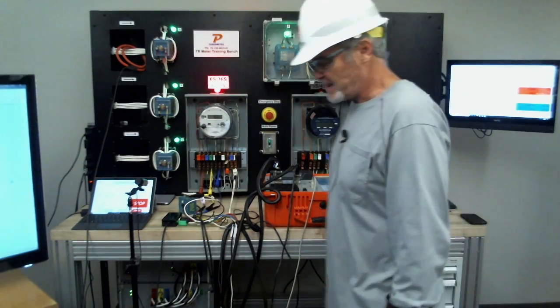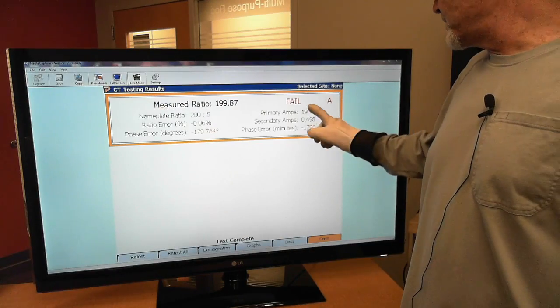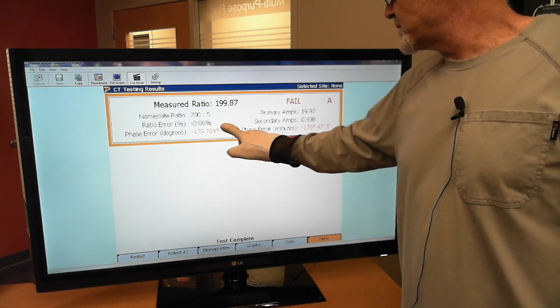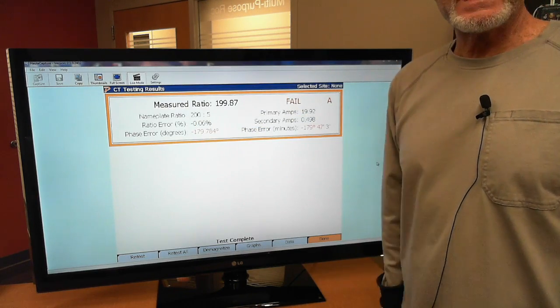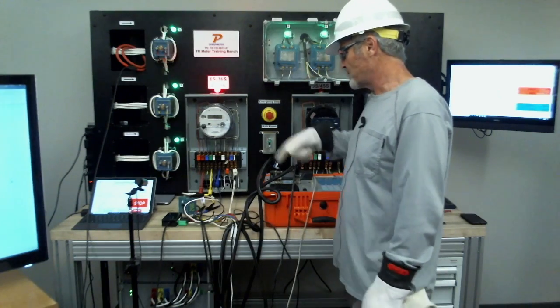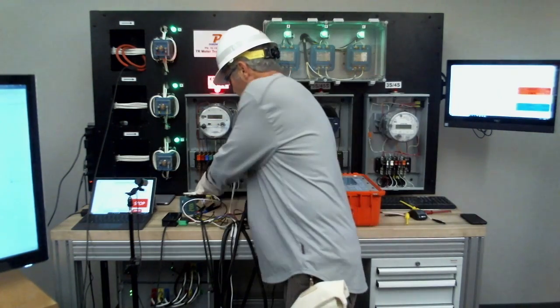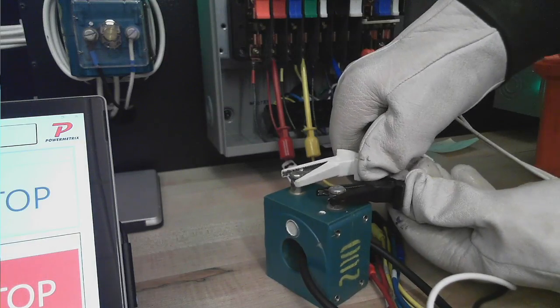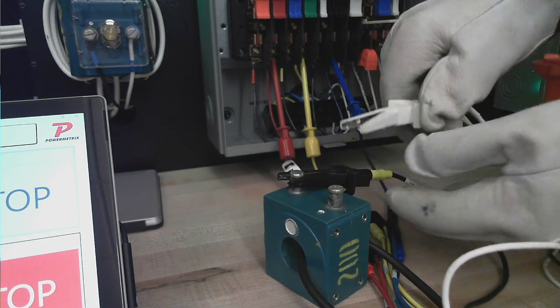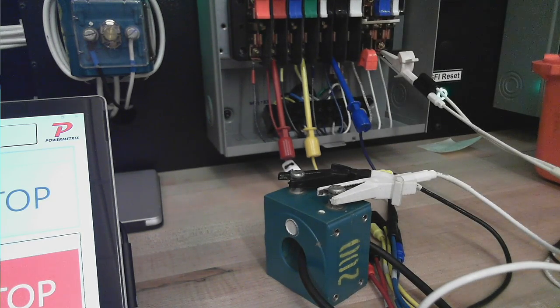And as we can see, we've said this before when we showed polarity reversal, red fail, and we always look, why did it fail? It's 180 degrees out, okay? And that is because of the polarity reversal that we've got right there. So if we swap them and retest, should come out fine.